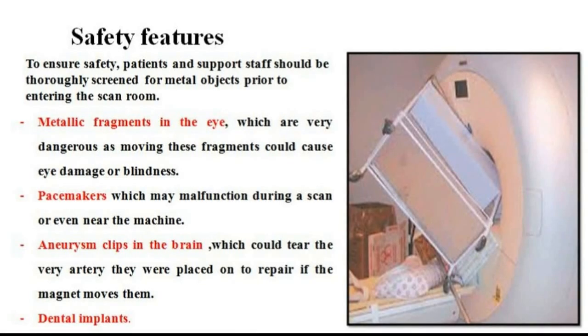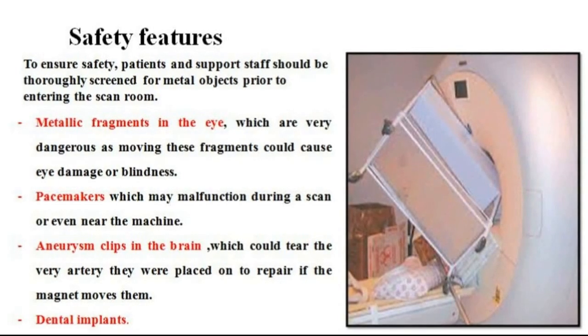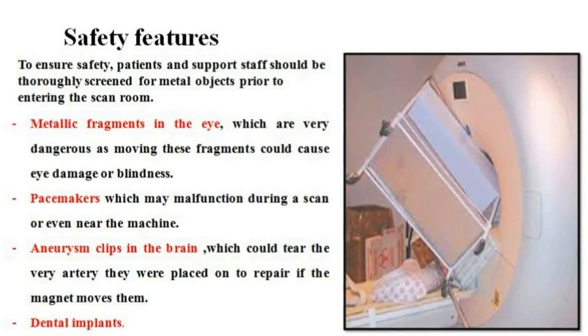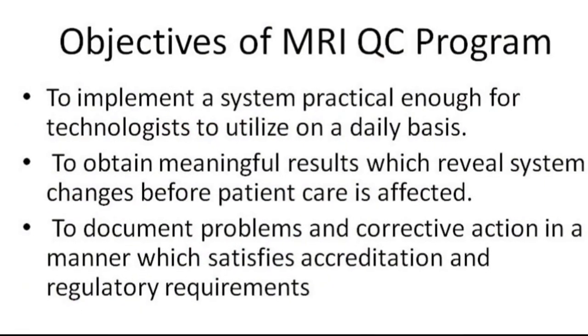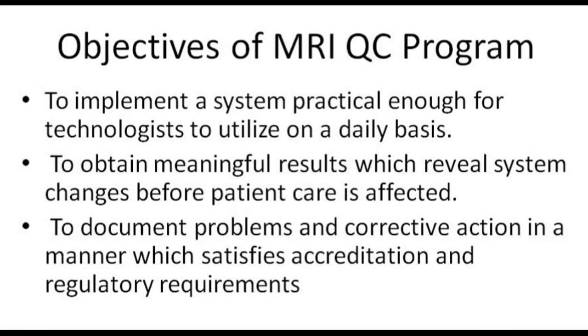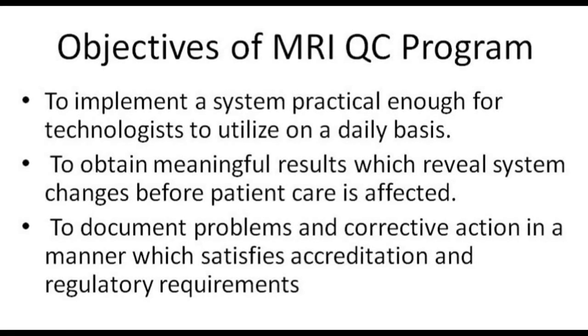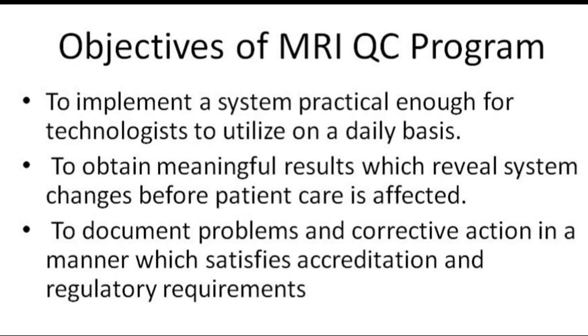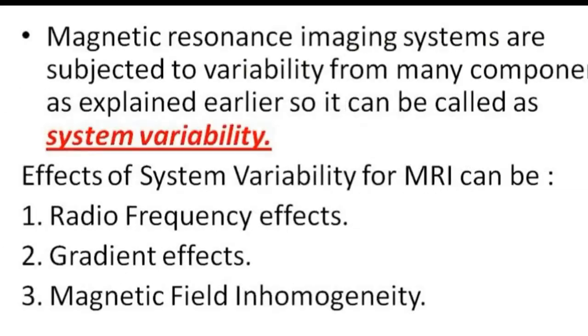These include metallic fragments in the eye, pacemakers, aneurysm clips in the brain, and dental implants. The objective of an MRI quality control program is to implement a system practical enough for technologists to utilize on a daily basis to obtain meaningful results which reveal a system change before a patient's care is affected, and to document problems and corrective action in a manner which satisfies accreditation and regulatory requirements.